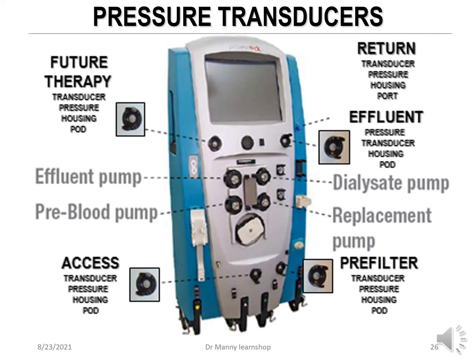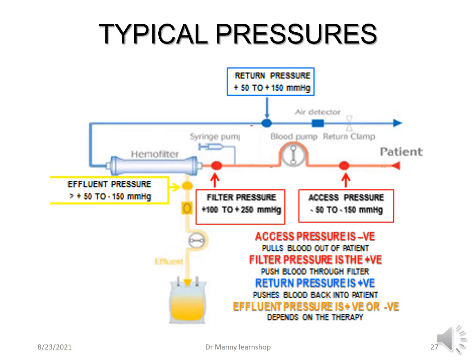Pressure transducers indicate the pressure, positive or negative. And sometimes, depending on the therapy, it can be positive or negative, especially the effluent. Typical pressures are these. The access pressure is negative because it has to pull blood out of the patient, the red line. The filter pressure is positive because it's got to push the blood through the filter. The return pressure is positive as well because it has to push blood back into the patient. The effluent pressure can be positive or negative. It depends on which therapy is being initiated.